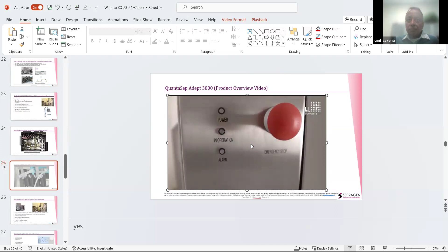In the unlikely event of a fluid leak, the base plate has been shaped so all the fluids are directed to a central leak sensor that has a threshold trigger of 3 milliliters or more, automatically shutting off the run and alerting the user.